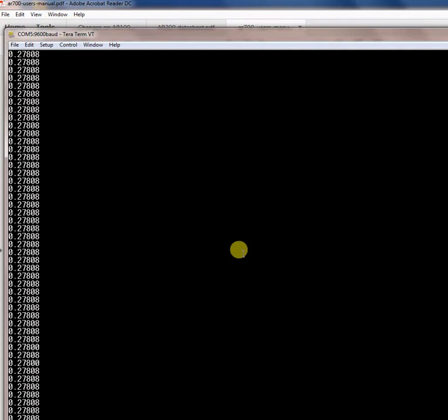So that's a hyperterminal, just a real basic communication program to the laser, but it gives you a lot of flexibility in setting your laser up. If you're not sure whether it's your laser or your power supply or your data acquisition, I would always say separate the laser from everything, go right into your hyperterminal and verify that the laser is working correctly.